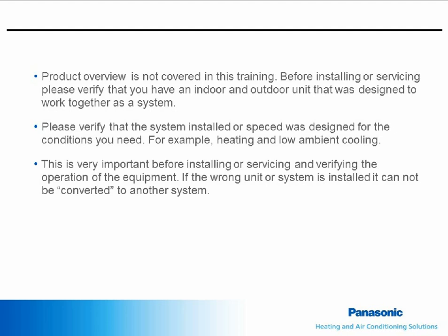Before unboxing the equipment, make sure that it is a match set and it is what you need for your specific application. For instance, make sure that the system is a heat pump if you need heat. If you need low ambient cooling, make sure the system you have purchased will provide cooling in these conditions. Make sure that the indoor and outdoor models are a match set or they may not even run. The indoor unit will give an error code if the system is mismatched.